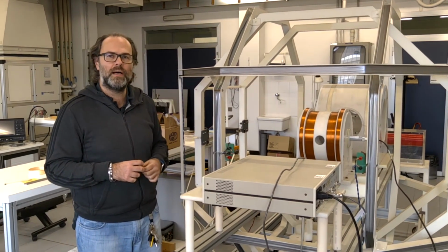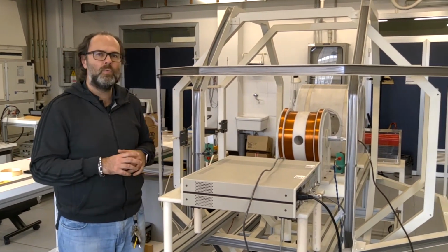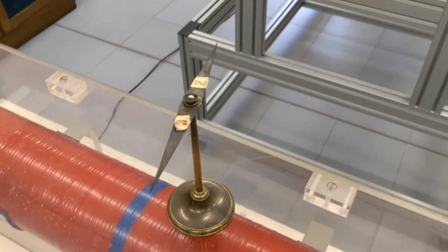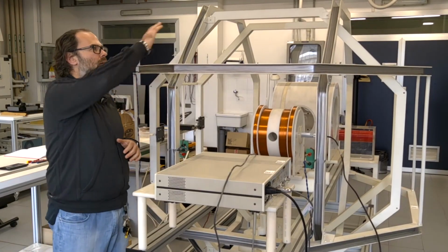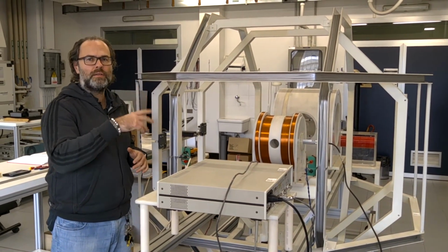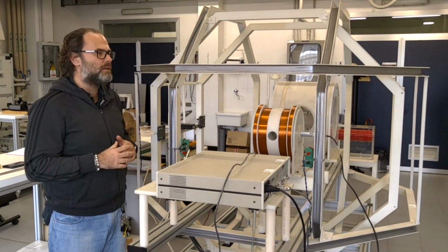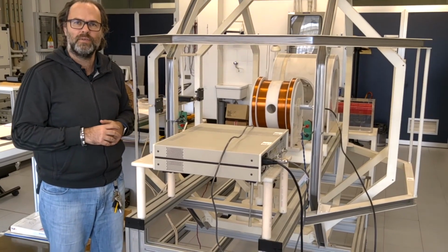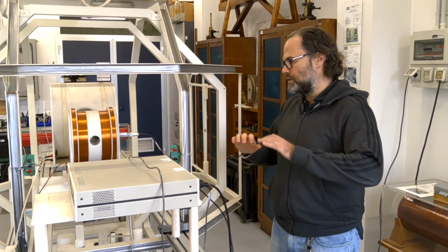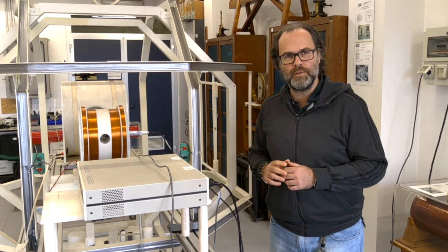The measurement will be done in a volume where the Earth magnetic field is close to zero. And this is done thanks to a set of 3 Helmholtz coils along the 3 X, Y, and Z directions that are used to compensate the Earth magnetic field. The first step consists in compensating for the Earth magnetic field.